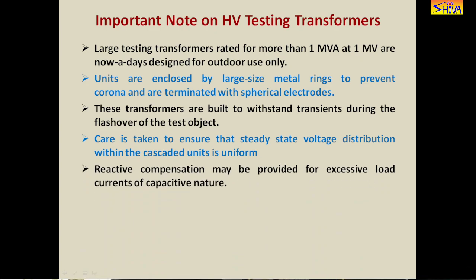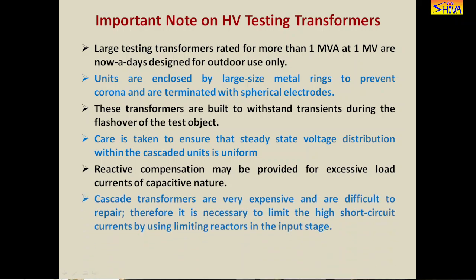Reactive compensation may be provided for excessive load currents of capacitive nature. The reason is that test objects are capacitive in nature, therefore they develop reactive power which needs to be compensated. Finally, cascaded transformers are very expensive and difficult to repair. Therefore it is necessary to limit high short circuit currents by using limiting reactors in the input stage to avoid damage to the transformers.